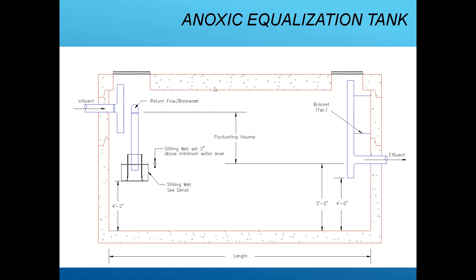The anoxic equalization tank is dual purpose — it serves as both an anoxic tank and an equalization tank. Solids settle out in this tank. There's a stilling well on the left-hand side for the return from the effluent tank, which prevents disturbance of the settled solids. Inflow comes in from the left and gravity flows out through the right. The operator monitors sludge level periodically and has sludge pumped periodically to keep it below the outlet to the next tank.